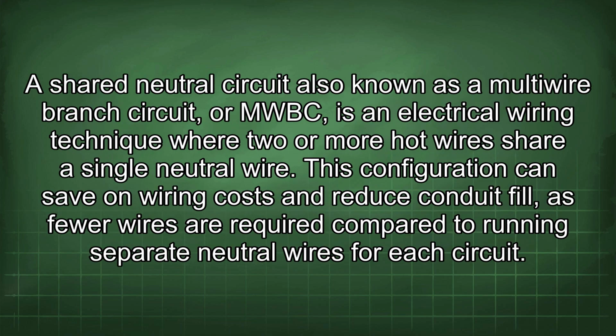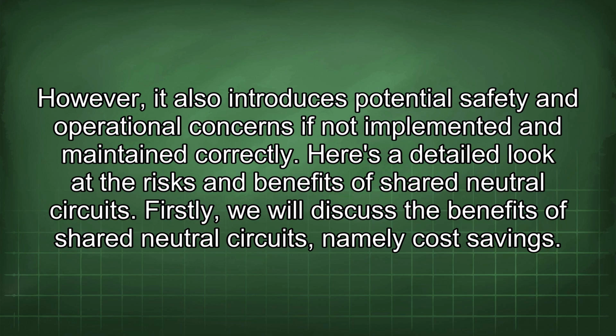A shared neutral circuit, also known as a multi-wire branch circuit, or MWBC, is an electrical wiring technique where two or more hot wires share a single neutral wire. This configuration can save on wiring costs and reduce conduit fill, as fewer wires are required compared to running separate neutral wires for each circuit. However, it also introduces potential safety and operational concerns if not implemented and maintained correctly. Here's a detailed look at the risks and benefits of shared neutral circuits.